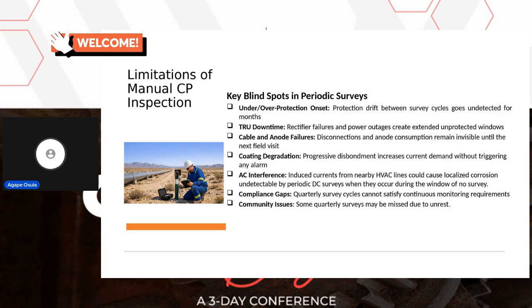And when you come again after the next CIPS survey and then you see that, you cannot begin to do tuning. That means for a significant period of time, something will happen to your TRU and you were not aware. Now, some people say, okay, we do monitoring. We go to look at the TRU every 3 months, for TRU inspection and the like. So your electrical team can do that. That's important. But if you do it every 3 months, perhaps I think the only alternative is to make sure that you are precise in this TRU downtime. So do it every day, right? So that at least when your TRU is down, you know instantly, and then you implement remedial actions. So this is also one of the drawbacks of this manual method.